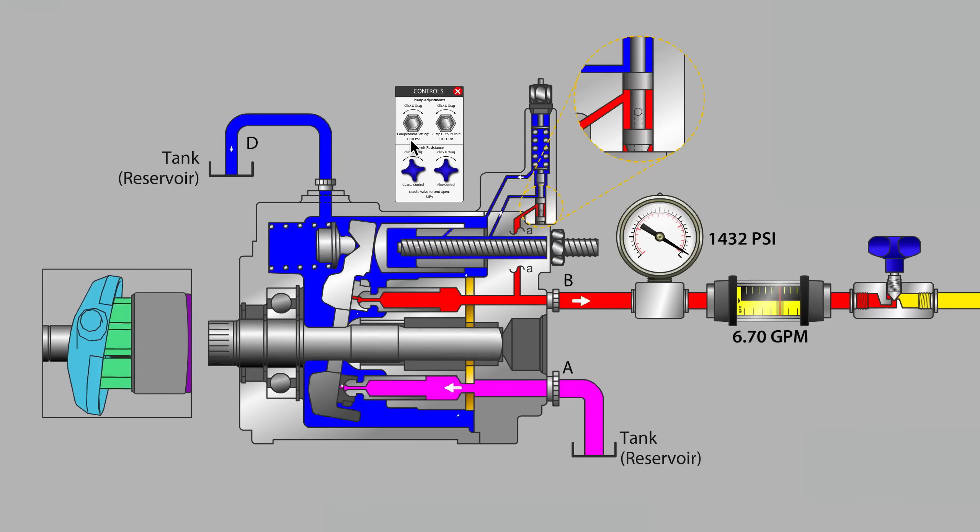Our maximum system pressure was set at 1500 psi and here we are above 1400. We're very close to the top pressure and so a pump that has the ability to be variable displacement is now showing that it has changed the angle of the swash plate.